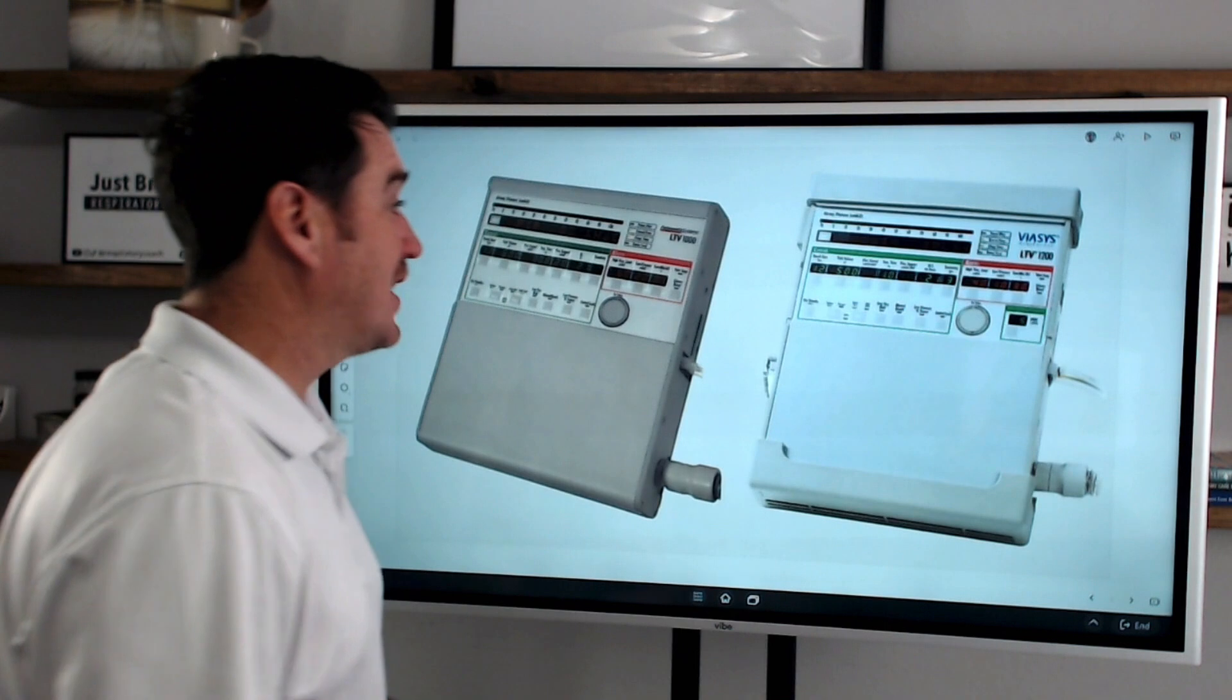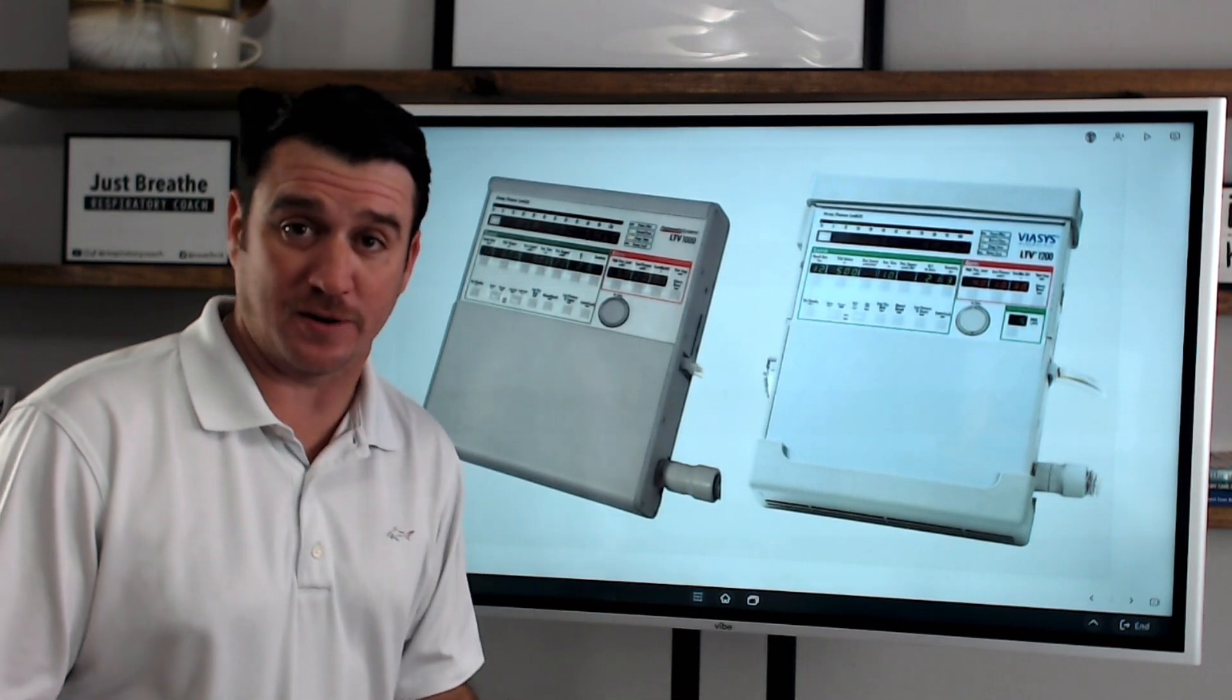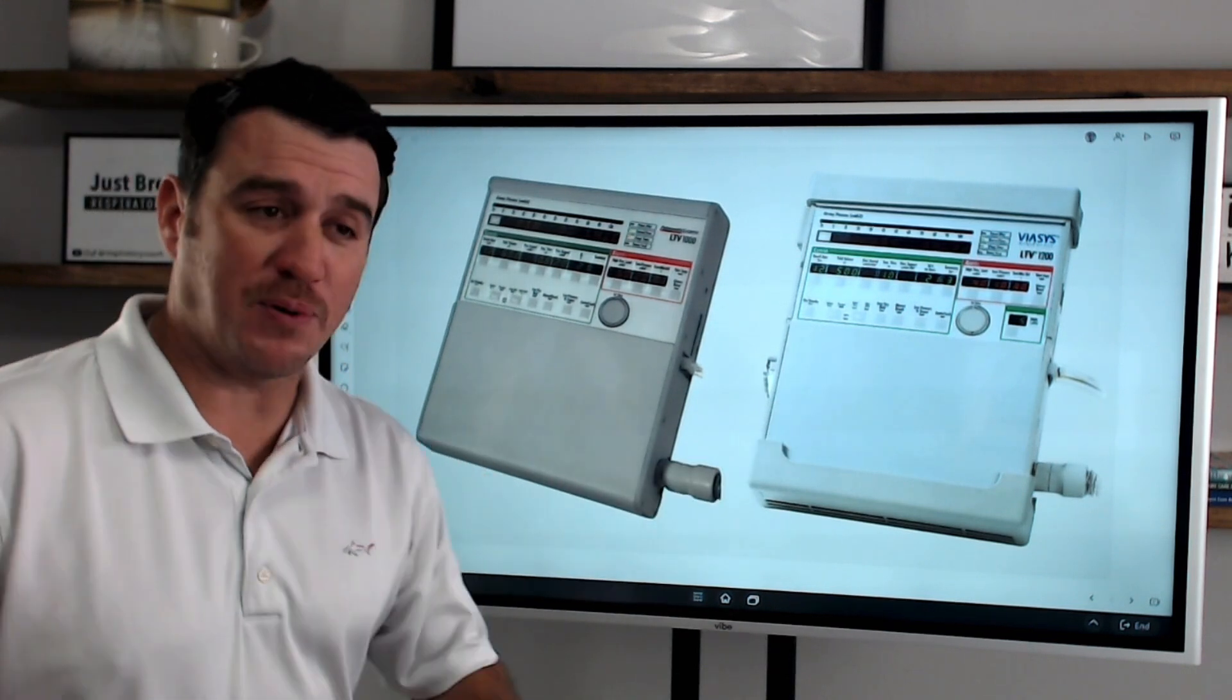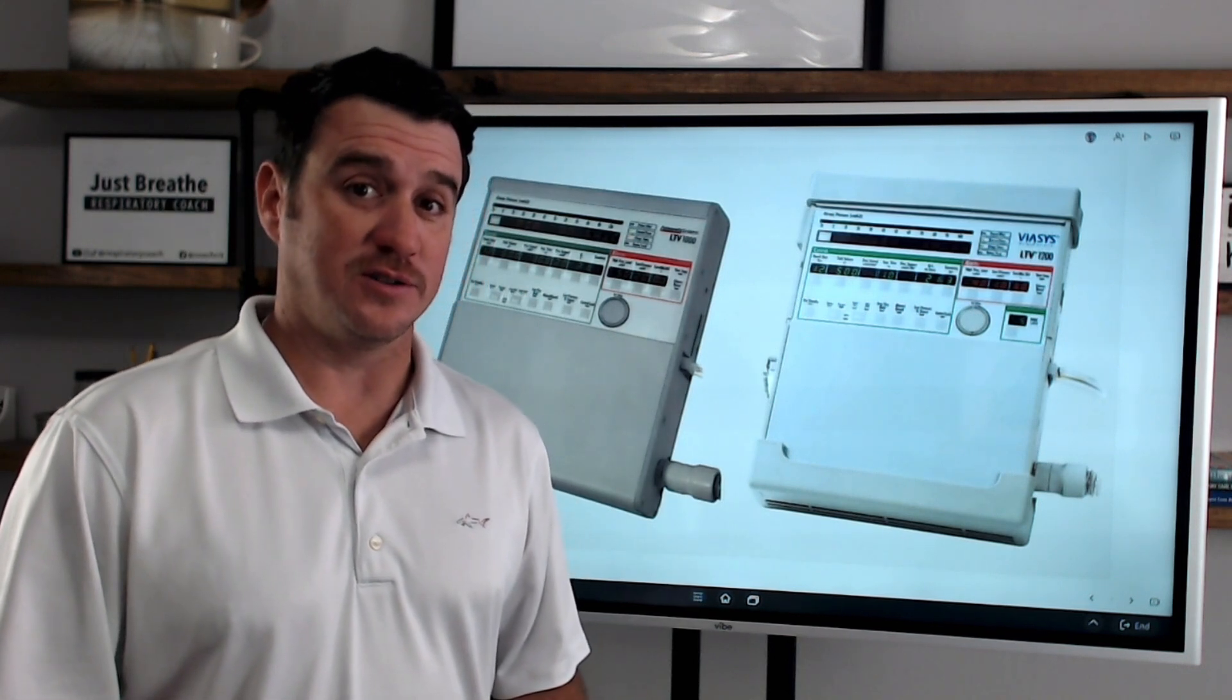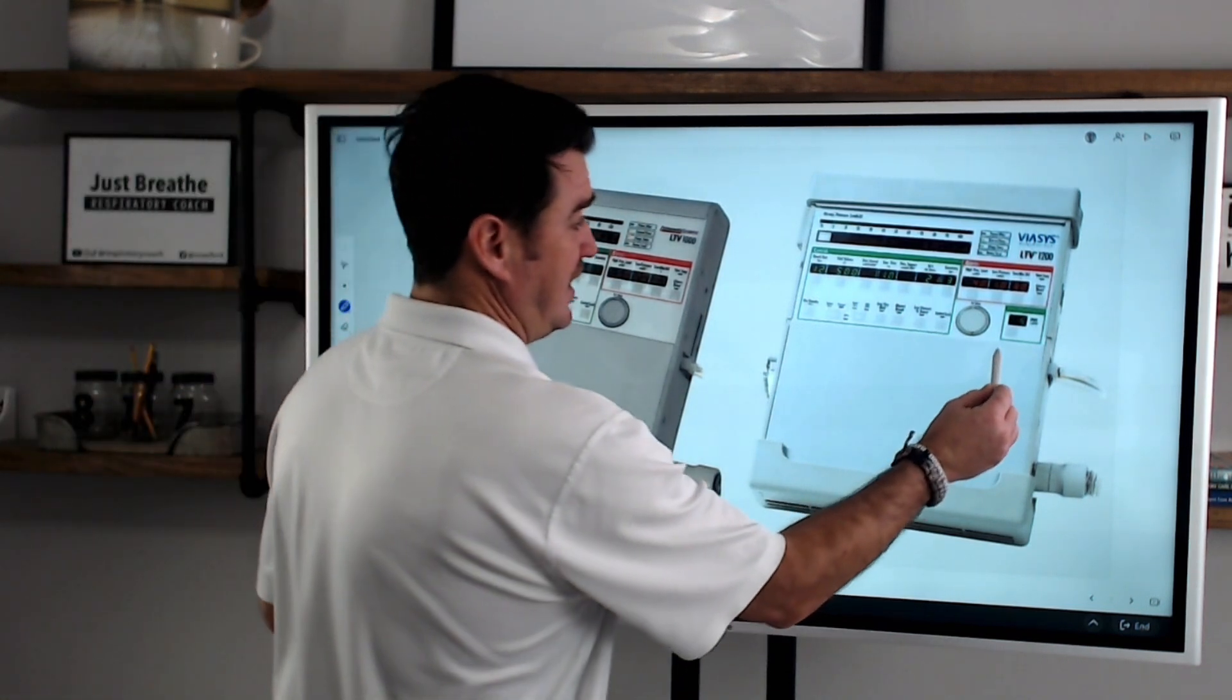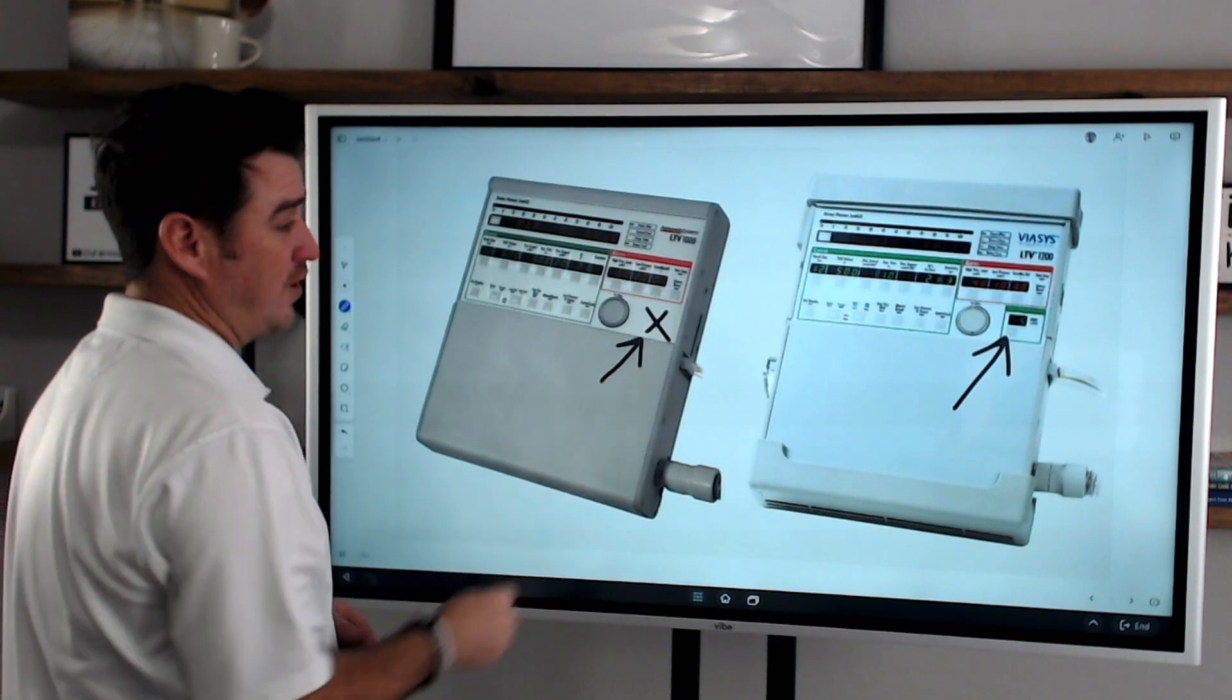Before we do that, let's go back to where we opened this video and can you tell me the difference between these two ventilators? Now on the surface, they look very similar. If you've worked with the LTV-1000 or the LTV-1200, then you probably know what the difference is. If you're new to these two ventilators and you don't know what the difference is, you're going to want to pay attention. If you notice right here, there is a box. That box does not exist over here.